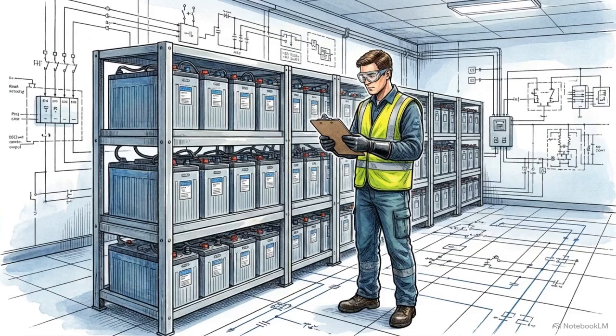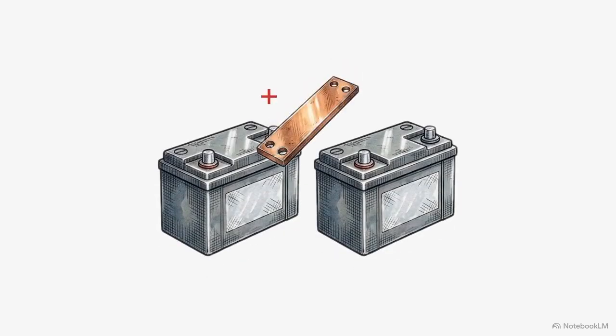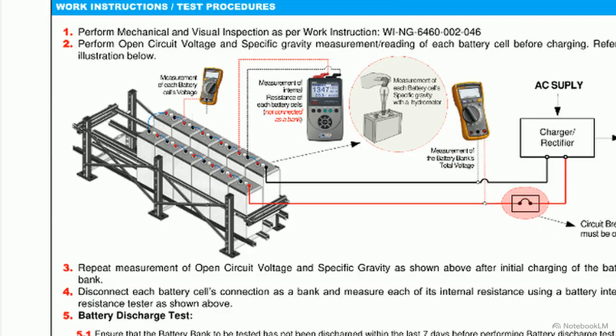Once safe access is established, the validation begins with a mechanical inspection of the battery rack. Every cell's polarity, the physical integrity of its connecting links, and the torque marks on the bolts must be explicitly confirmed. This schematic highlights the next step: measuring the initial open circuit voltage of every single cell using a digital multimeter. This establishes our baseline and must be done before any charging occurs.